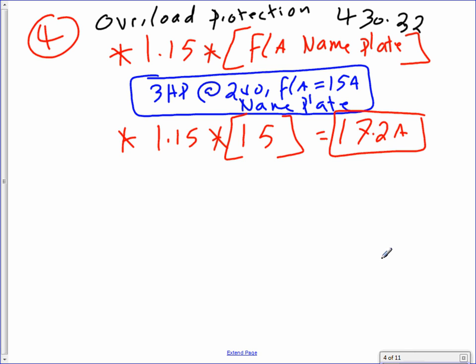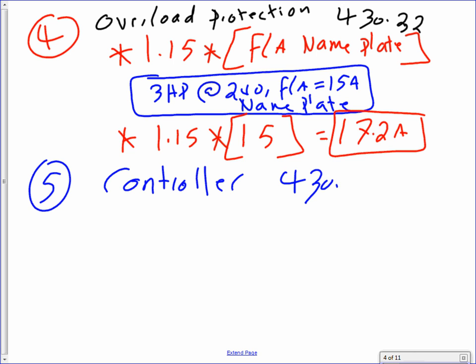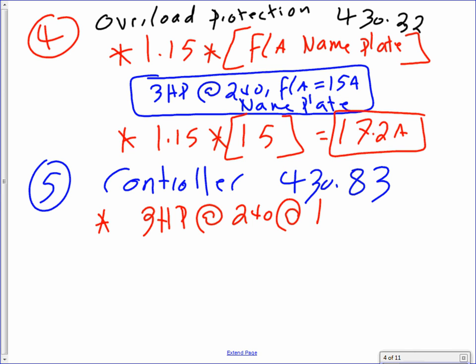Number 5 is controller. For controller, you need to go to 430.83. 430.83 is your controller. Okay? Here's what the controllers are rated for. It will tell you it has to be rated for 3 horsepower at 240, single phase. That's how, when you buy a controller for a motor, Karen, you're going to pick up the phone and call Viking and say, hey, I need you to get me a single phase 240 3 horsepower controller.